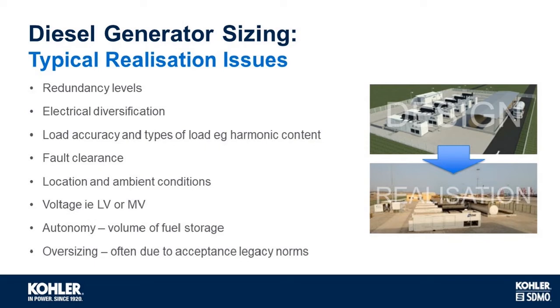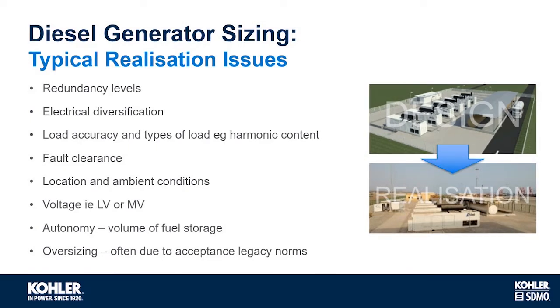Some considerations around distribution. So is an LV generator set or an MV generator set the best option? Of course, autonomy, the amount of fuel that needs to be stored. And as I touched on earlier, it's critical that the engine is not oversized. However, this often happens due to applying historic legacy norms.